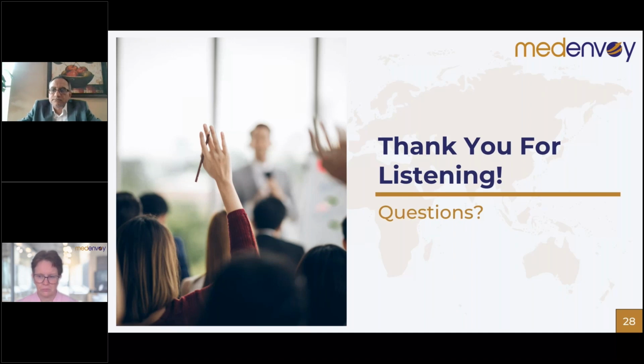Great, thank you. Next question: is PMCF required for all medical devices, or are there specific scenarios where it is mandatory under the MDR? Post-market clinical follow-up, as we explained, the requirement fundamentally is to assess the risk management, the residual risk, and how those are being managed. But even if there is no residual risk or no outstanding untreated risk, you still have to have a plan. So there's no exception for not having a post-market clinical follow-up plan. You must have a plan. Whether you need it or not depends on the risk management and the clinical efficacy and the context in which the device is being used.